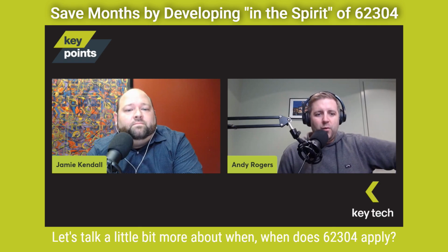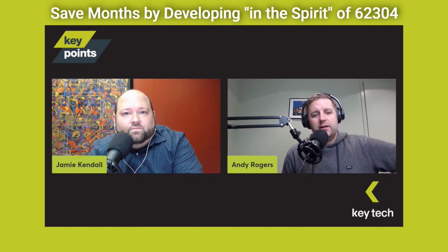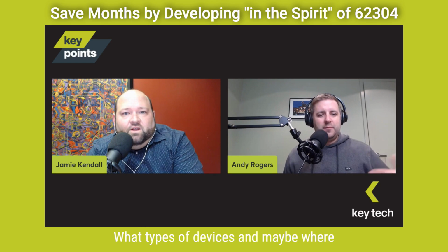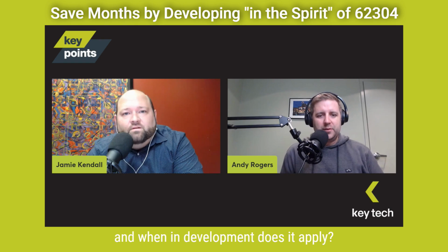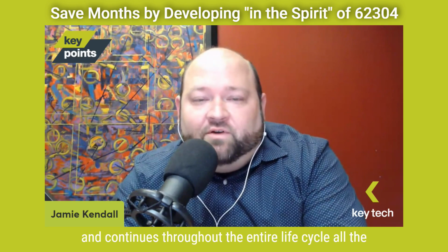Let's talk a little bit more about when does 62304 apply? What types of devices, and maybe where and when in development does it apply? It starts from really the beginning of the process, starting with your requirement generation and continues throughout the entire life cycle, all the way to your formal testing or formal verification.